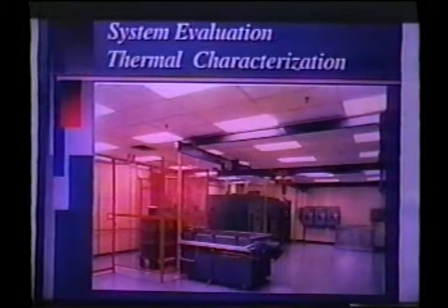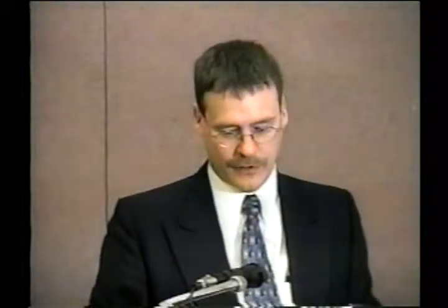After a prescribed period, a motorette, which is a small stator I'll show a picture of next, is taken from the oven, put onto a shaker table where it is shaken, then it's taken into a 100% humidity chamber, which is shown in the forefront, and after being in there for a prescribed period, it's given a high pot test. If the samples pass, they continue to go through the testing until all the samples fail. So this is a very good test for determining the thermal rating for an insulation system.